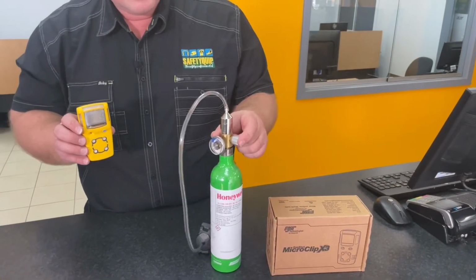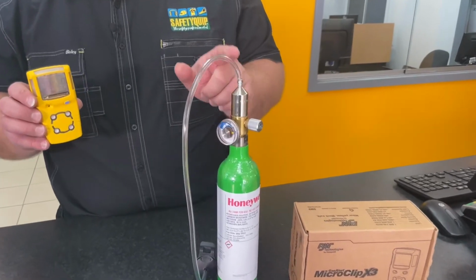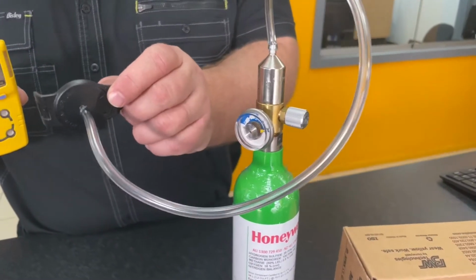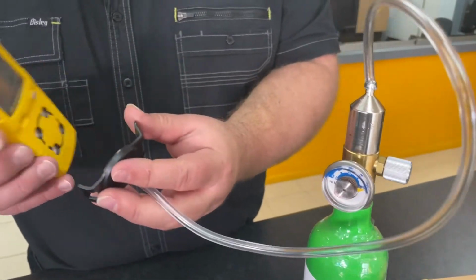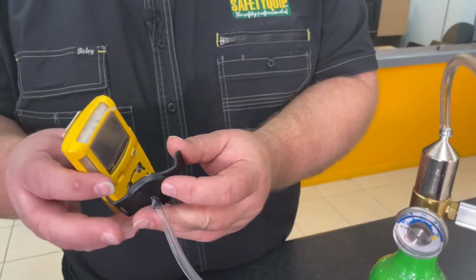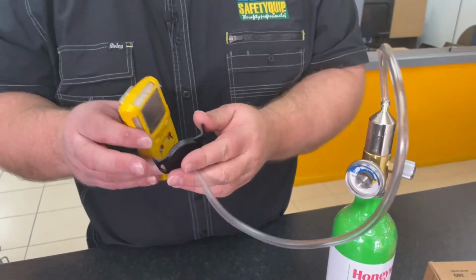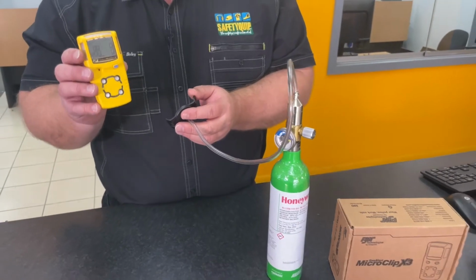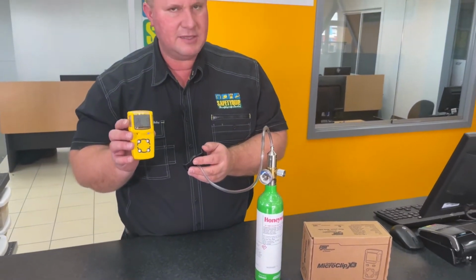Now I've got a regulator on the top of the gas cylinder, and I've got a tube down to, we call this a test cap, this black bit on the end. That clips on the front of the gas detector and allows us to feed the gas into the gas detector to enable us to recalibrate the gas detector.